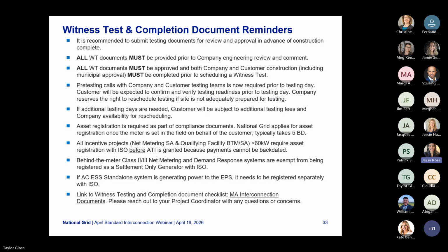Make sure the witness test checklist includes pictures of the generator nameplate capacity. Remember that all checklist requirements must be approved by National Grid, and all customer construction must be completed before scheduling a witness test. With regard to compliance and asset registration, National Grid will manage the registration process with ISO New England unless the customer desires otherwise.